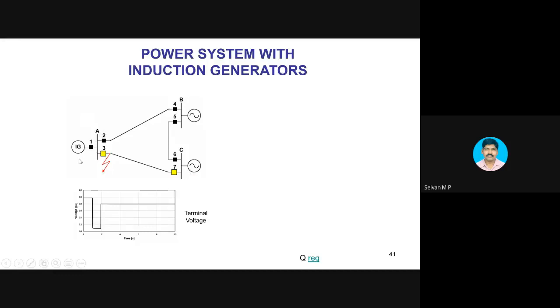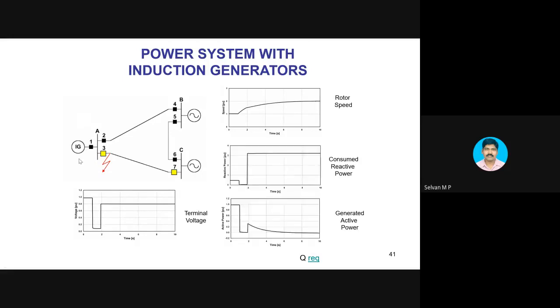We will see what is happening to this machine. I will put all the graphs. When the system is healthy and the voltage is 1 per unit, the machine is operating just above synchronous speed, delivering 1 per unit real power to the grid, and it is drawing around 0.6 per unit of reactive power from the grid. The system is healthy. Suddenly there is a fault and the voltage drops. As soon as the voltage drops, the active power generation becomes zero. Why does it become zero? Since the voltage has dropped, there is no voltage to maintain a magnetic flux in the machine, so there is no reactive power flow into the machine. Reactive power becomes zero because the voltage has dropped to a very low value.